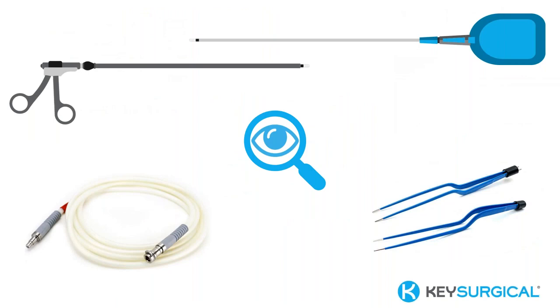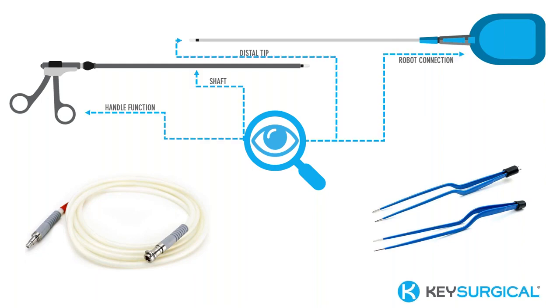In the decontamination area and in the pack and prep, we take care and attention when handling these items. Using laparoscopic instruments and robotic arms as our primary example, never grab by the shaft or the distal tip, as this can cause damage to the instrument. Care and attention is critical in handling any of these items. For distal tip inspection, use lighted magnification to see the distal tip, like Michelle previously mentioned. Insulation damage is most common in the 1/3 tip, so having lighted magnification on the pack and prep side is necessary for thorough inspection. Next up we have the bipolar forceps: inspect the tip for any frays and check the connection end to make sure that all the parts are there and nothing is cracked, missing, or broken.